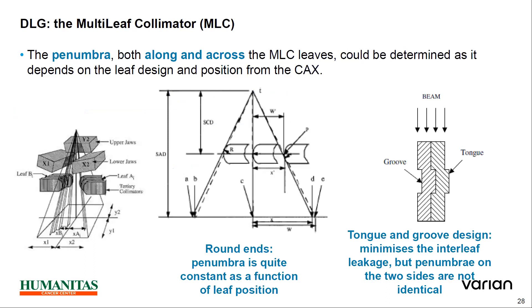For the multi-leaf collimator, we need to understand MLCs for the DLG. Elekta has a different system and Varian has a different system, so one has to be aware during commissioning. The penumbra along and across the MLC direction depends on leaf design and position. The tongue-and-groove effects minimize interleaf leakage, but the values on the sides are not identical.